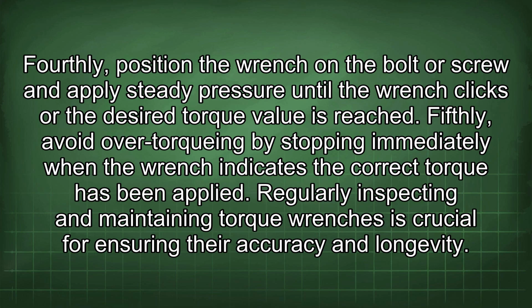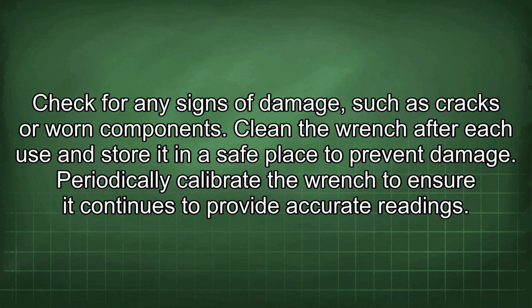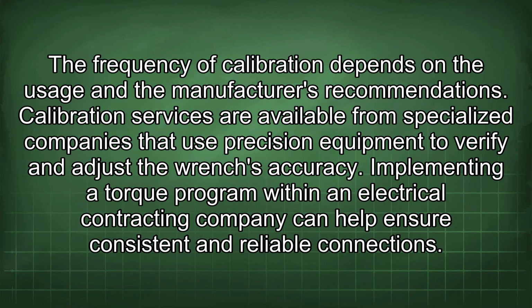Regularly inspecting and maintaining torque wrenches is crucial for ensuring their accuracy and longevity. Check for any signs of damage, such as cracks or worn components. Clean the wrench after each use and store it in a safe place to prevent damage. Periodically calibrate the wrench to ensure it continues to provide accurate readings. The frequency of calibration depends on the usage and the manufacturer's recommendations. Calibration services are available from specialized companies that use precision equipment to verify and adjust the wrench's accuracy.